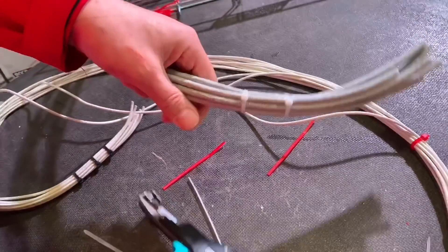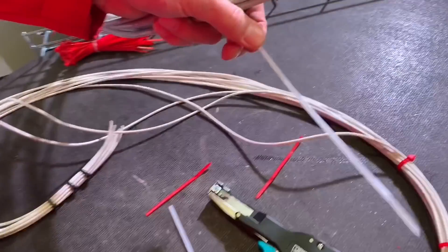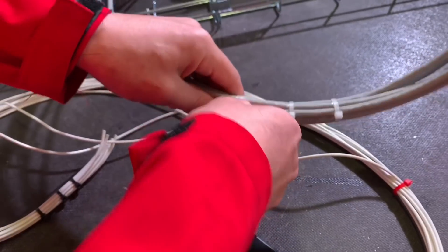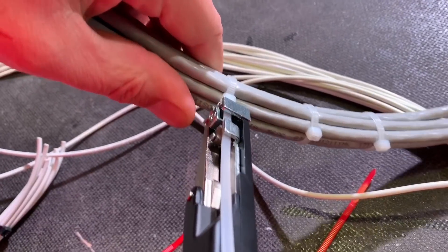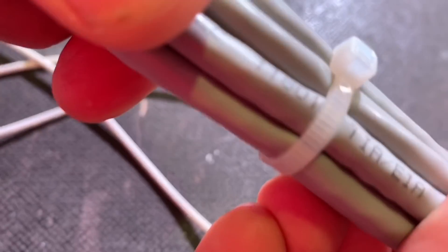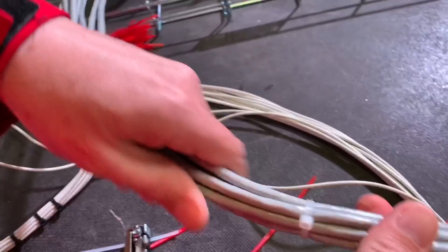Let's go to three now. So what we're trying to replicate here is how hard maybe an electrician is pulling these cable ties in order to secure them to a basket or a tray. Phoenix Contact lives in that panel building world - we've looked at the CrimpFox on the channel before, which was a four-in-one tool for doing ferrules. This is now 11 kg. So let's see whether the cable tie can cope. You saw that - pull those conductors. Yeah, that's really biting in. That is really, really squashed now. But the cable tie can do that - it's within its parameters, but I would suggest it's not doing any favours to the conductors themselves.